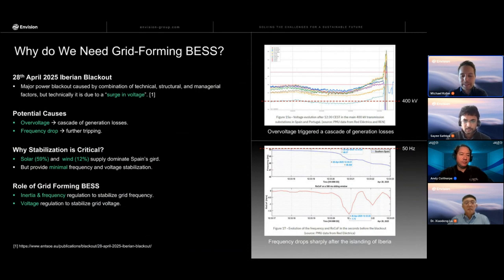I personally was in Spain that day. It's quite an interesting experience to have a 12-hour blackout. Interesting things start to happen. So it's something to take seriously, I would say, at least. And when you look at the cause of this event in Iberia, it's similar at a high level to all these kinds of events and outages. It's a cascade and multiple factors going together.